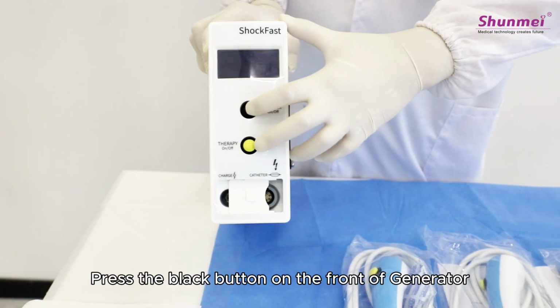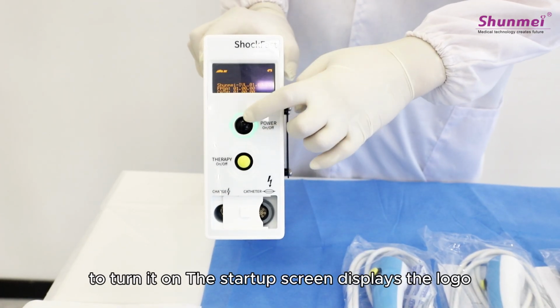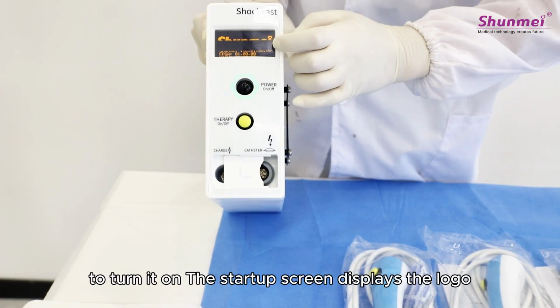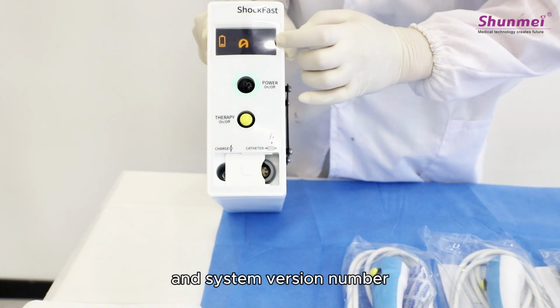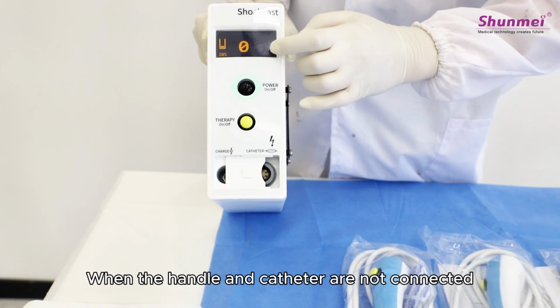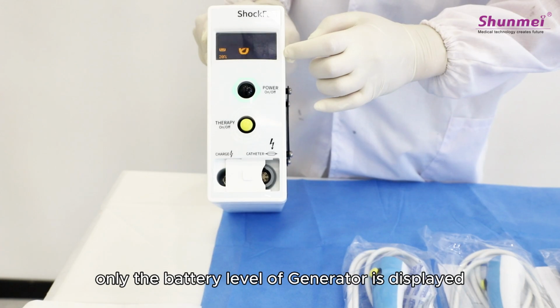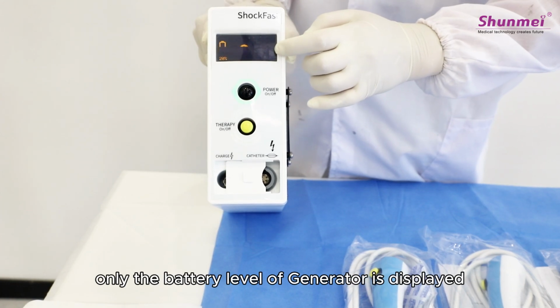Press the black button on the front of the generator to turn it on. The startup screen displays the logo and system version number. When the handle and catheter are not connected, only the battery level of the generator is displayed.